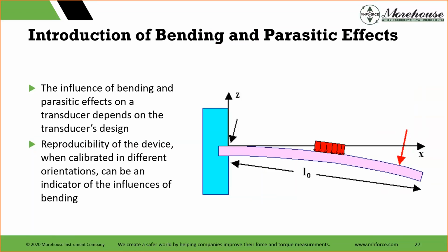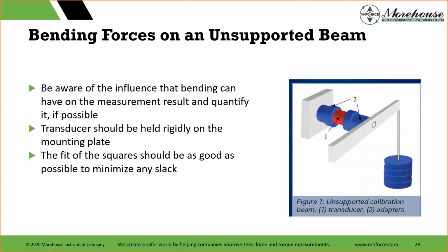If you want to test this, rotate that cell 90 degrees, rotate that square drive and try and see how good it is, right? That's what we're saying about calibrating in a different orientation. Do more than one run on it. Get your numbers. Ideally, you probably do two runs with it at the same spot to get repeatability numbers, and then start putting it in a different orientation and seeing if it repeats. If it doesn't repeat, you could have some additional bending. And next, we're going to talk about bending forces on an unsupported beam, which are really, really common. And NPL did this awesome study with Norbar, and they wrote a paper, and this is what came from it.